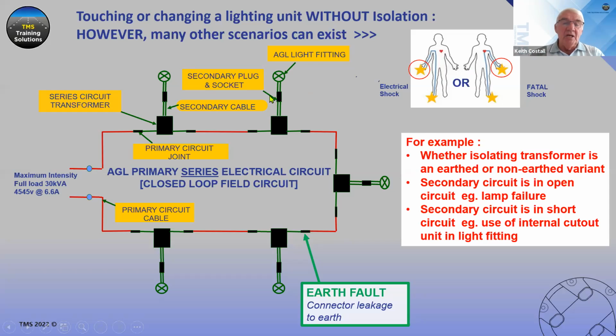Has the lamp actually failed? Because when the lamp fails, this is an open circuit. So if this is an open circuit, then this isolating transformer can go into saturation. When it goes into saturation, it's no longer a transformer. So now we have the potential of a higher voltage on the secondary side. So those are just some other examples of what can happen.